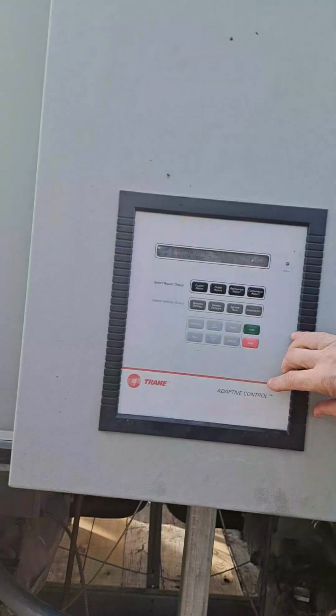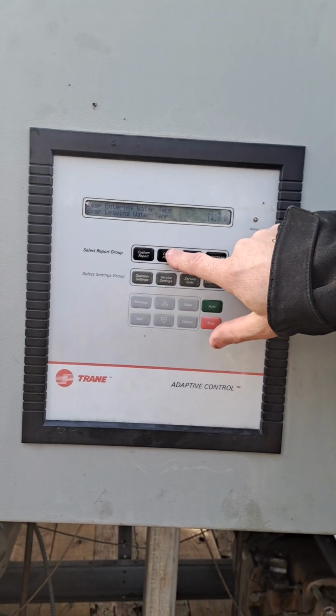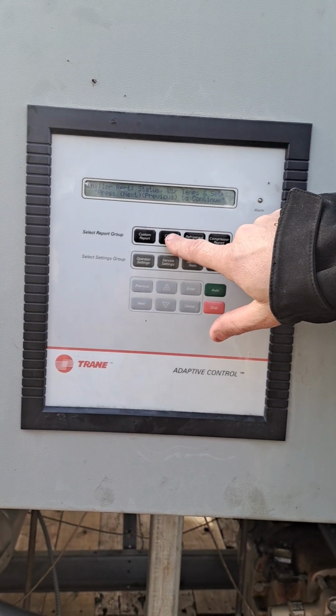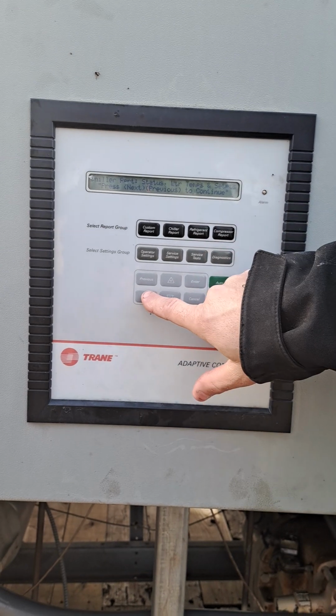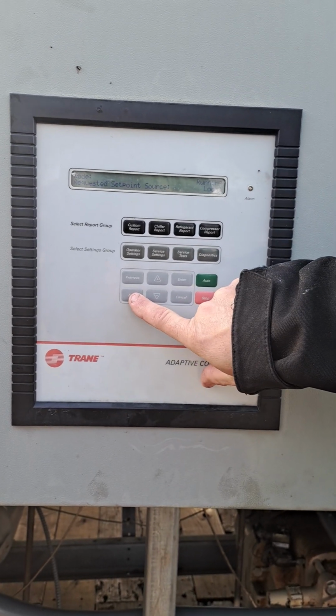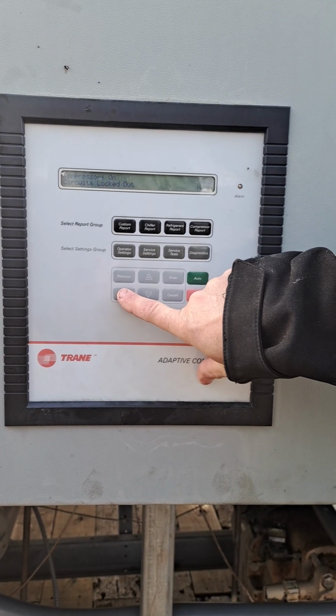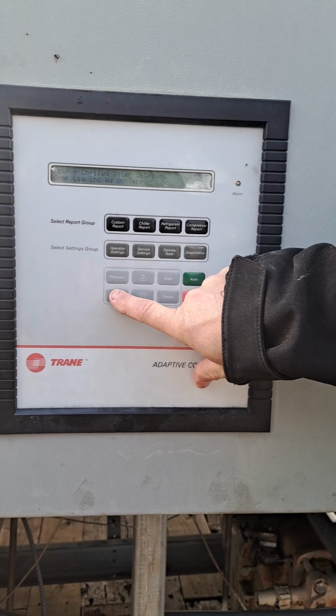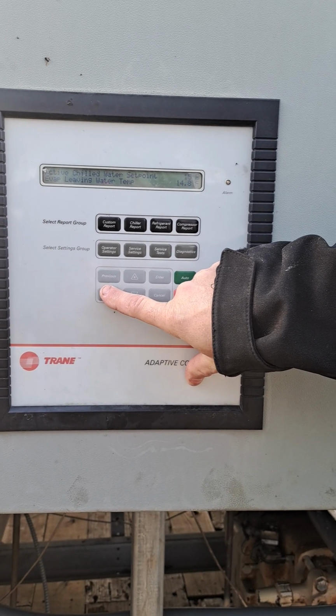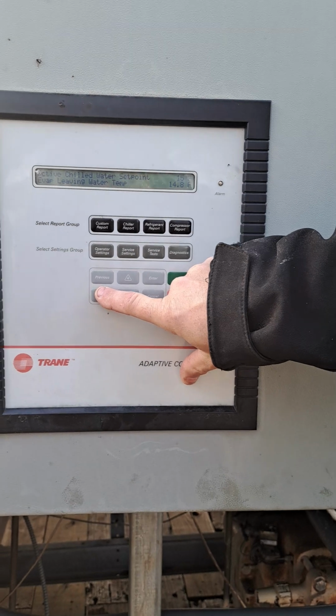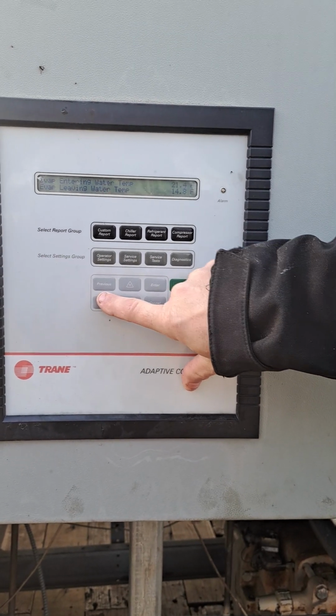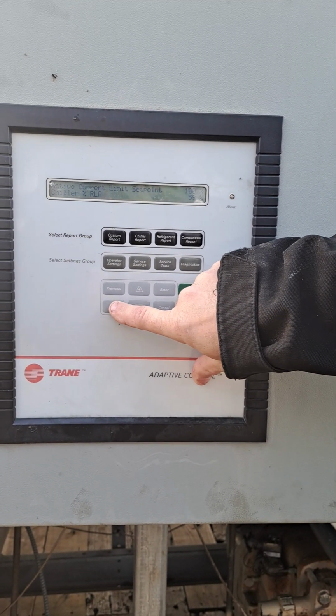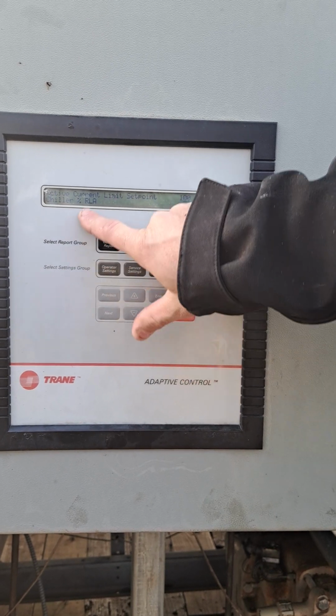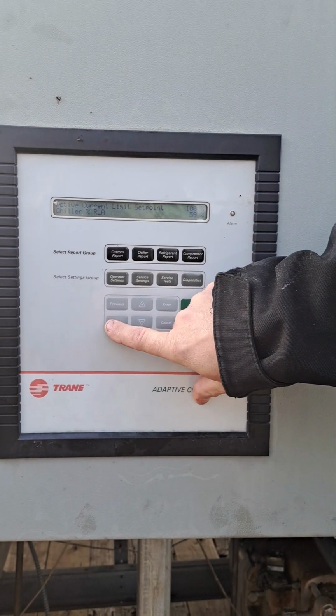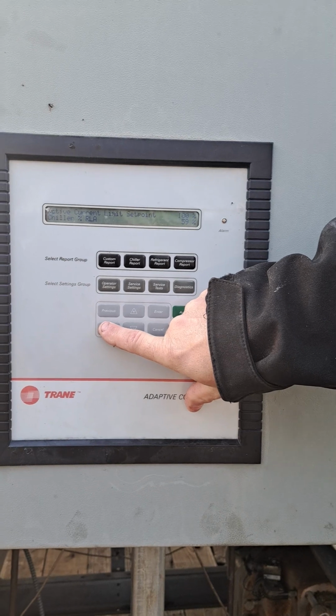So here's your interface system. Chiller report shows you all the status of the chiller. Hit next. It says you're running in local mode. Shows you both compressors are running. Nothing's locked out. This is your entering and leaving water temperature. So you just scroll through to get your data for that. You're running 59% of full load amps right now, so it's not even running 100%.